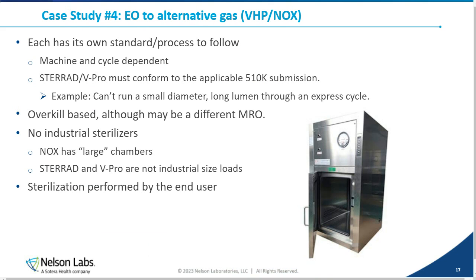So our next and final case study is going to be when we're changing from EO to an alternative gas. That's a broad category. We're going to lump in vaporized hydrogen peroxide and the Noxilizer, for example. A big consideration here is that each one of these is going to be its own validation. So the STERRAD, there are different machines and different cycles, same with V-PRO. Just like EO is cycle and chamber dependent, very much the same case applies when we're using those alternative gases. The other thing is those alternatives really haven't been set up on an industrial scale. There are not really industrial sterilizers made to use large amounts of vaporized hydrogen peroxide or the Noxilizer.